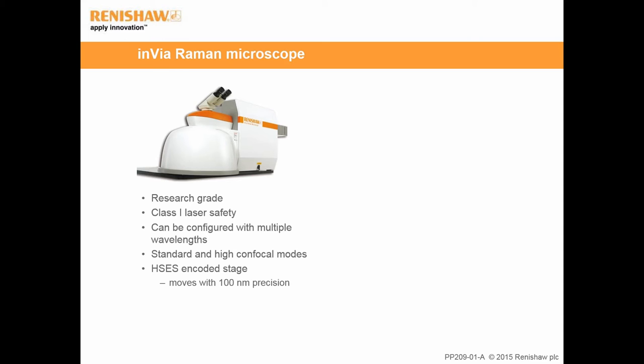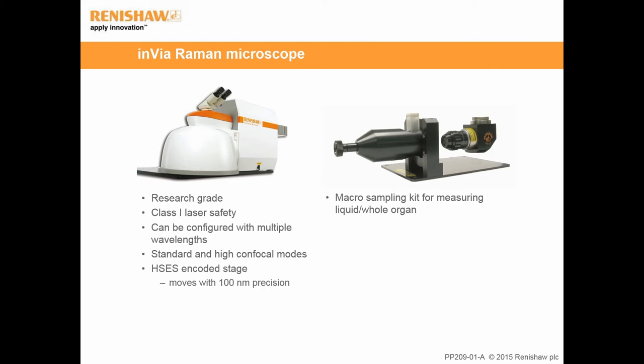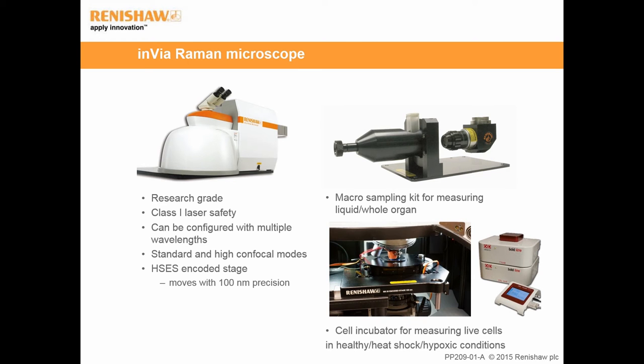The Renishaw inVia is a research-grade Raman microscope with a class 1 laser safety design. It can be configured with multiple laser wavelengths and high or standard confocal modes to suit different research purposes. The high-speed encoded microscope stage moves with 100 nm precision. Different accessories and measurement modes are available for different samples: for liquids, the macro sampling kit; for live cells, the inVia can be coupled to an incubator for environmental control; and for tissue sections, StreamLine imaging — a fast mapping method using a line-geometry laser — is particularly suitable.